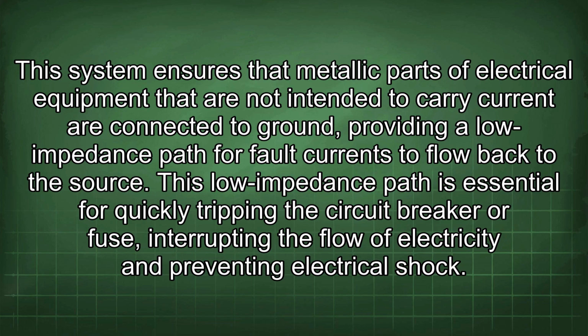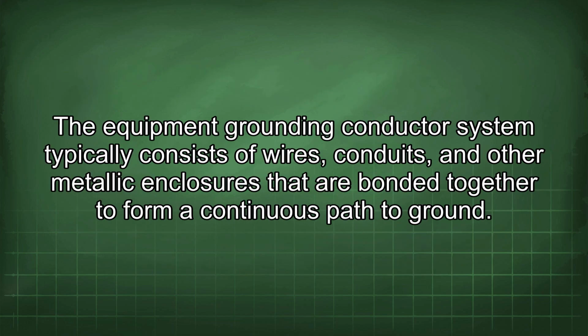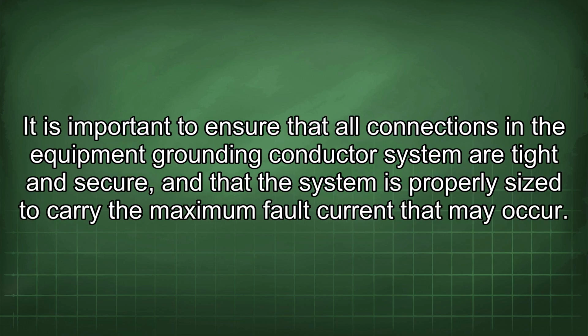This low impedance path is essential for quickly tripping the circuit breaker or fuse, interrupting the flow of electricity and preventing electrical shock. The equipment grounding conductor system typically consists of wires, conduits, and other metallic enclosures that are bonded together to form a continuous path to ground. It is important to ensure that all connections in the equipment grounding conductor system are tight and secure, and that the system is properly sized to carry the maximum fault current that may occur.